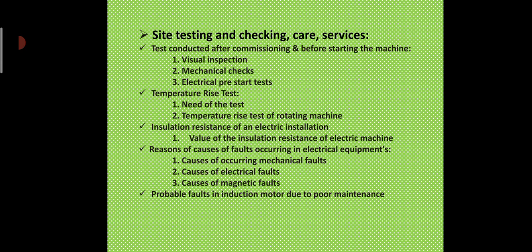Now, probable faults in an induction motor due to poor maintenance. An induction motor is a rotating machine, so its proper maintenance is necessary. First, connections of the terminals and earth become loose due to vibrations. Sparking may be the result. The terminal may get burnt and the motor can catch fire. If the connections are not made tight periodically, earth resistance increases if the earth connection gets loose. Temperature of the bearing increases, noise is produced, and the quantity of lubricant required increases if maintenance of bearings is not done properly.